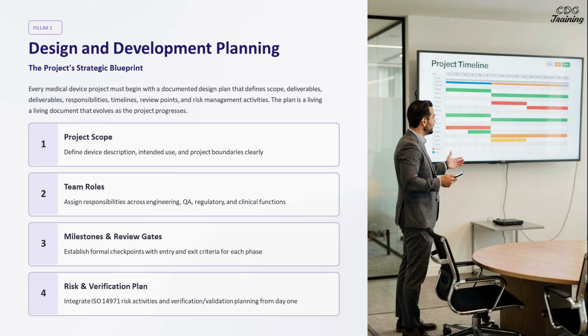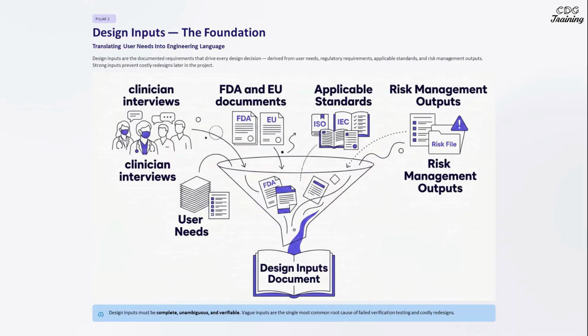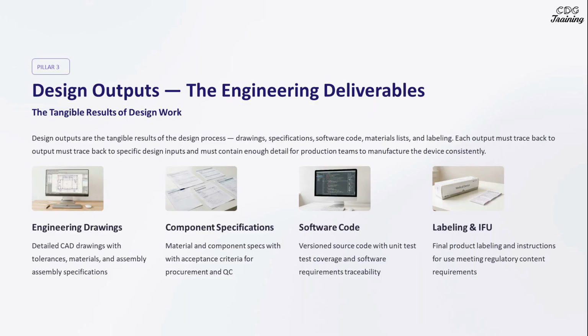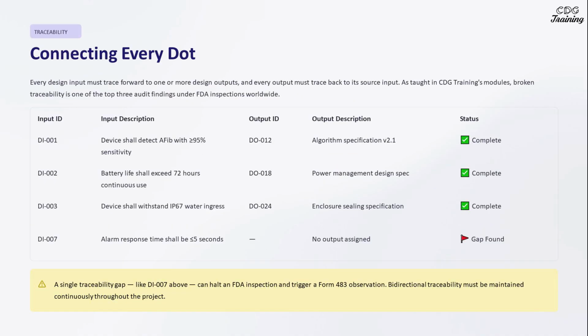Every medical device project starts with a documented design plan, defining scope, deliverables, and responsibilities, evolving as the project progresses. Design inputs translate user needs into engineering language, forming the foundation for the design process. Design outputs are the tangible results of the design process, including drawings, specifications, and labeling, ensuring consistent manufacturing. Every design input must connect to design outputs, ensuring traceability and compliance throughout the project.